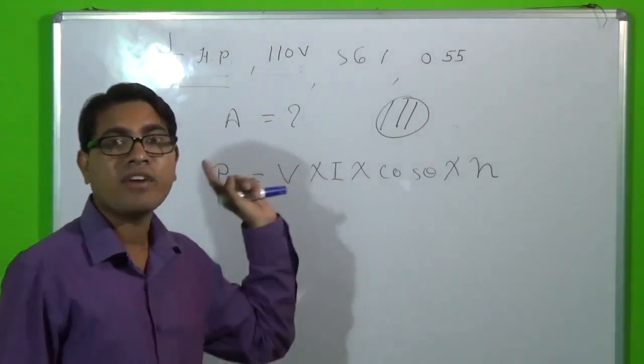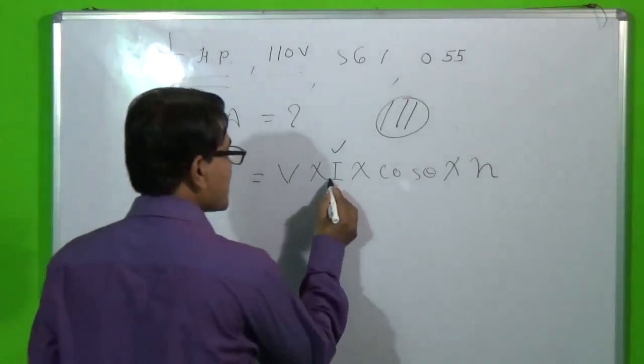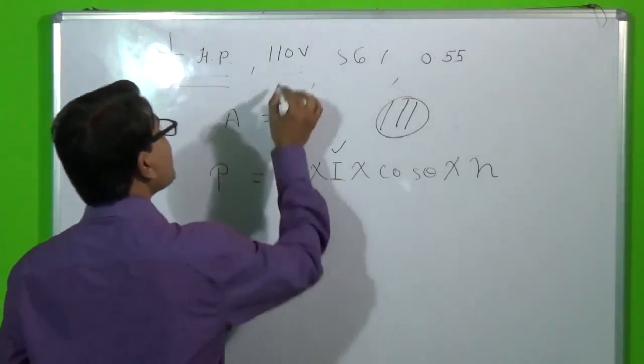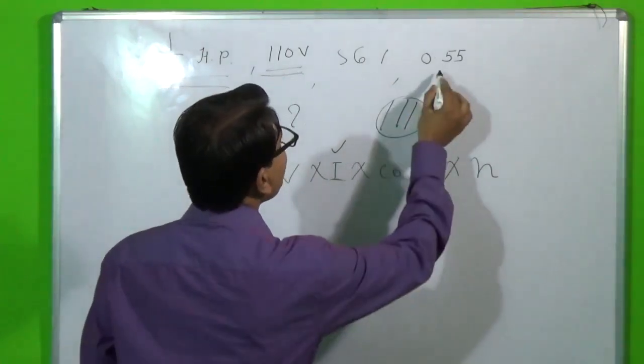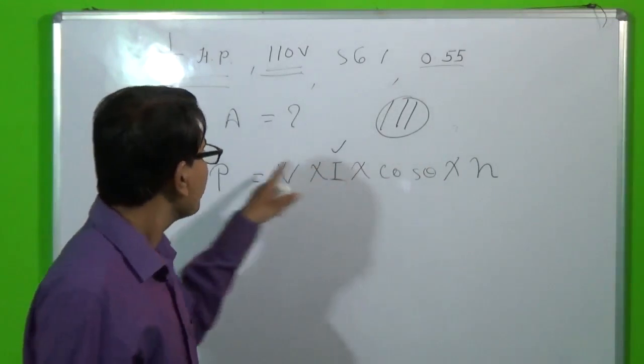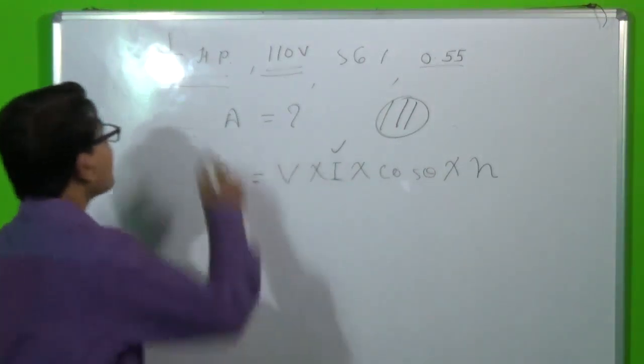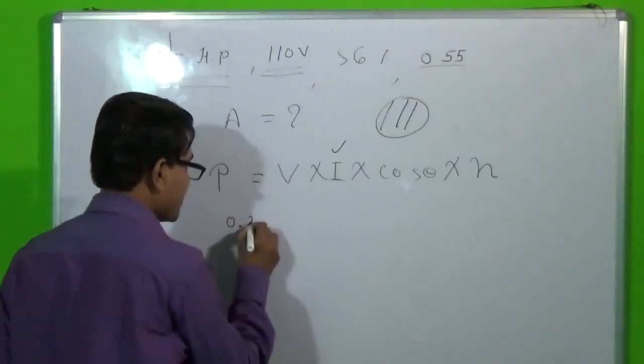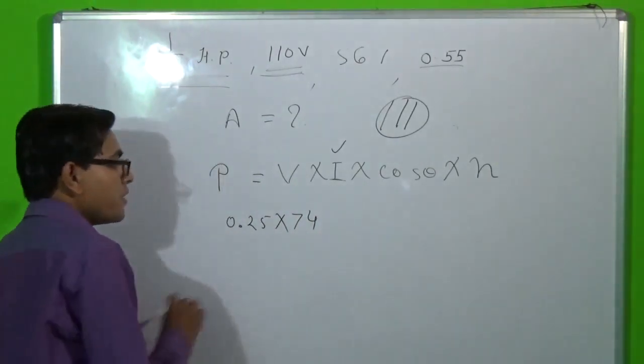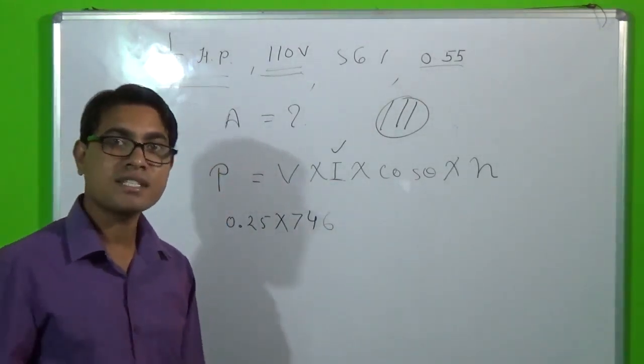We will use that formula and find out how much current our motor is taking from the supply. The power the machine is taking is 1/4 HP, the voltage is 110 volts, the power factor is 0.55, and the machine is 56% efficient. We will put all these values into the formula to find the value of current I. 1/4 HP means 0.25 HP, and to convert this into watts we multiply by 746 watts, because 1 HP equals 746 watts.